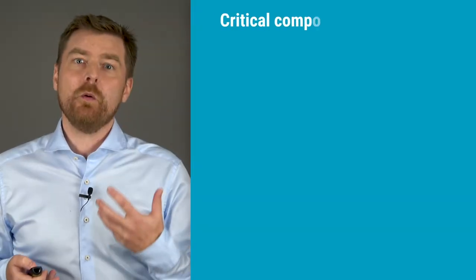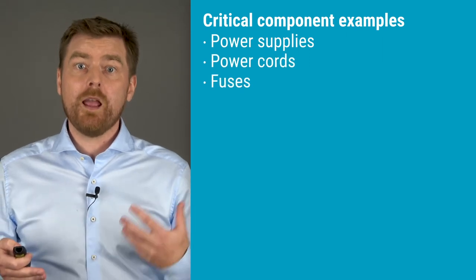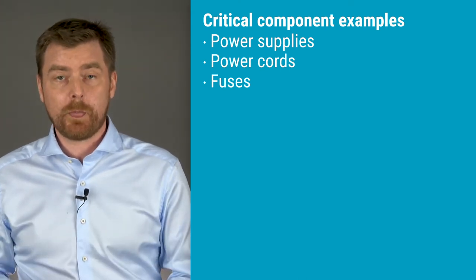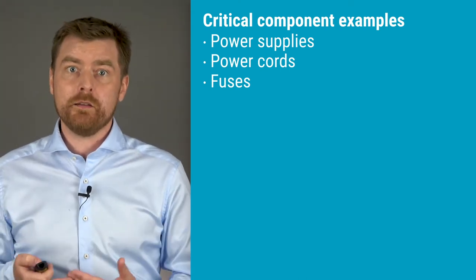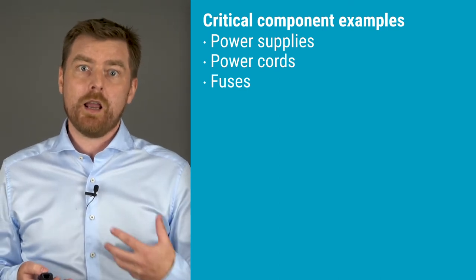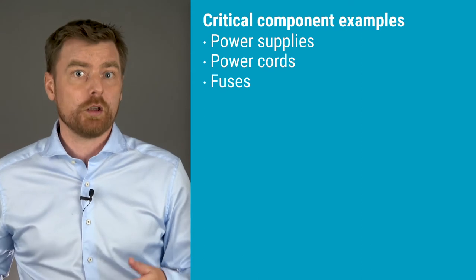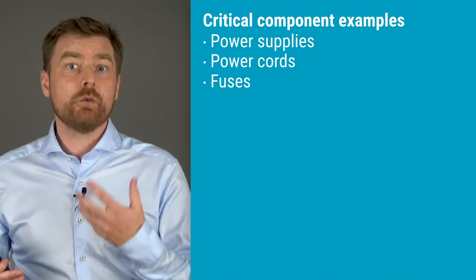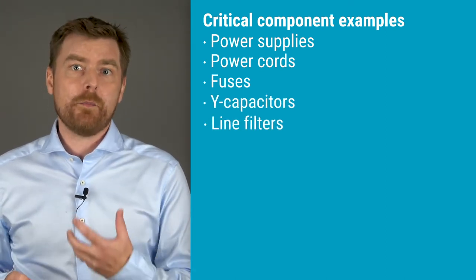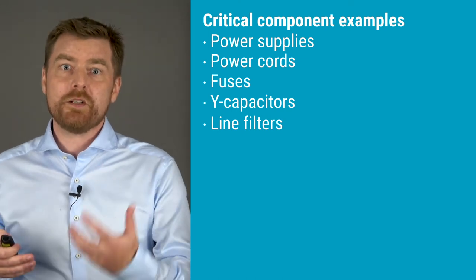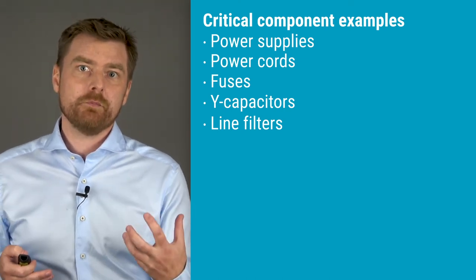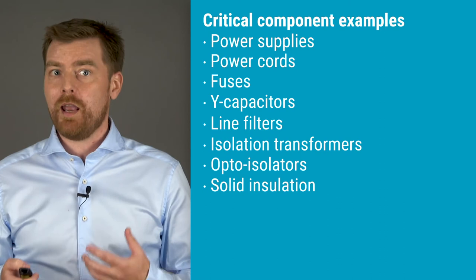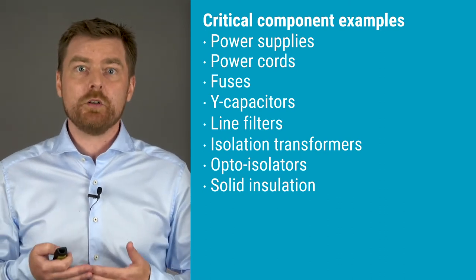Here are a few typical examples of critical components. A failure in any of these components can potentially result in a hazardous situation. A fault in the insulation barriers provided by power supplies and power cords can expose the user to electric shock. A fuse that fails as a short circuit does not limit the current to the device. A fault in a Y capacitor or a line filter can present line voltage on the chassis. A fault in isolating components such as transformers, opto-isolators, and solid insulation can expose the user to electric shock.